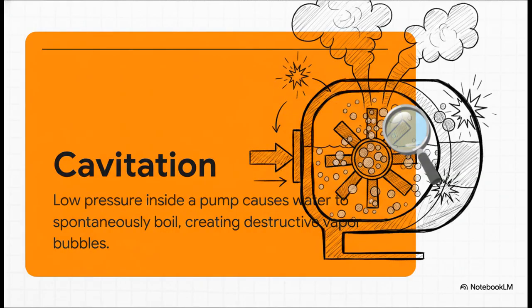You get this. Cavitation. Now, this sounds totally impossible, but the super low pressure inside the pump can actually cause the water to boil, even at perfectly normal temperatures. Tiny bubbles of water vapor, steam, just spontaneously form inside the pump. And trust me, these are not harmless little bubbles.